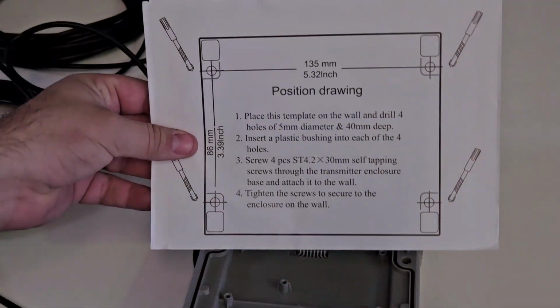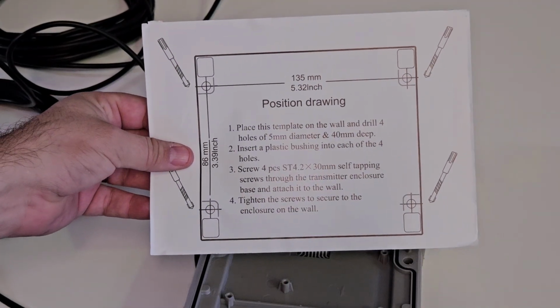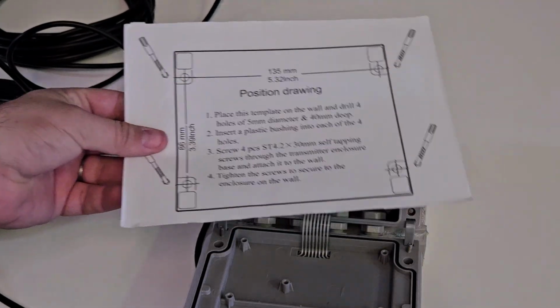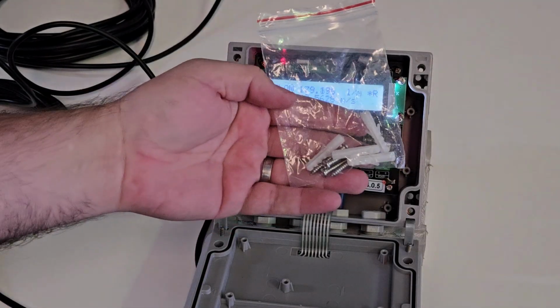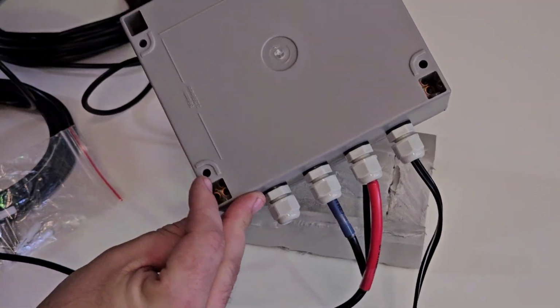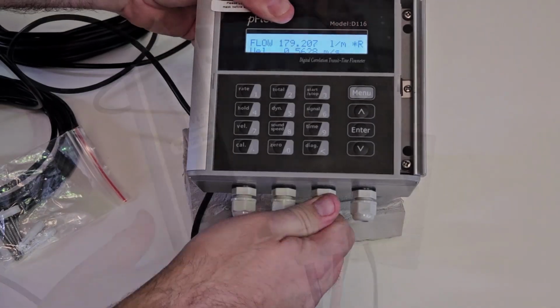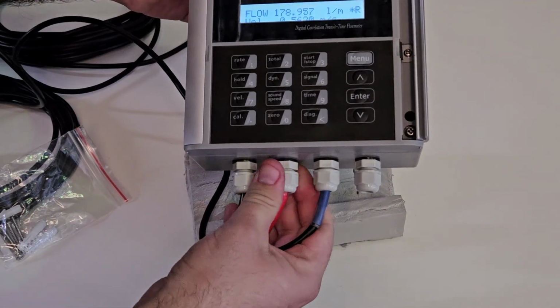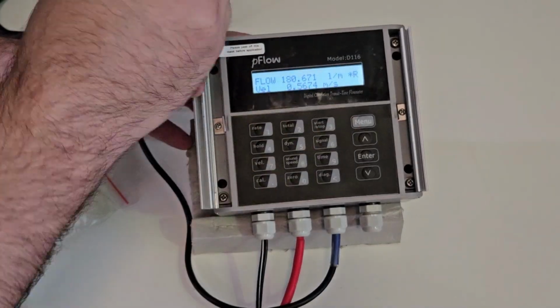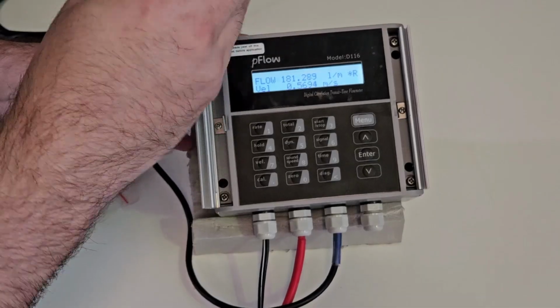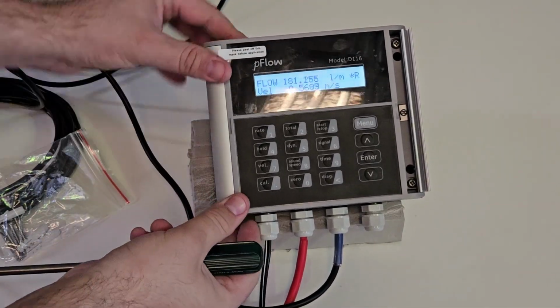Now everything is working. If required, you can wall mount the meter. You can use the template to drill and prepare mounting holes, then use the included wall plugs and screws. These holes shown are for wall mounting. Double check all your cable glands are tight. Then screw the case closed. 4 screws total, 1 in each corner. You can also close the hinged screw covers.